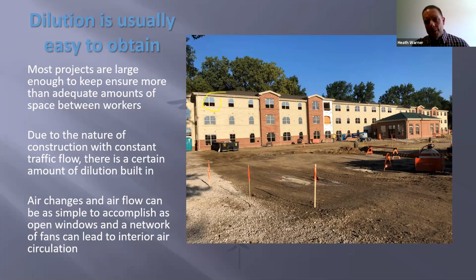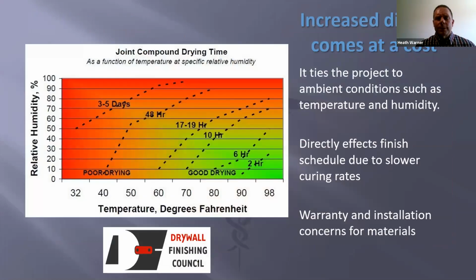You'll notice that there are no windows open on floor one or floor two, only windows on floor three. The problem with dilution for construction is you're tied 100% to the ambient environment, meaning your temperature, your humidity, it's whatever it is outside. I use the drywall finishing council graphic because I think most people recognize it at this point, but it's probably the best representation of what is actually going on when you're tied to ambient conditions.